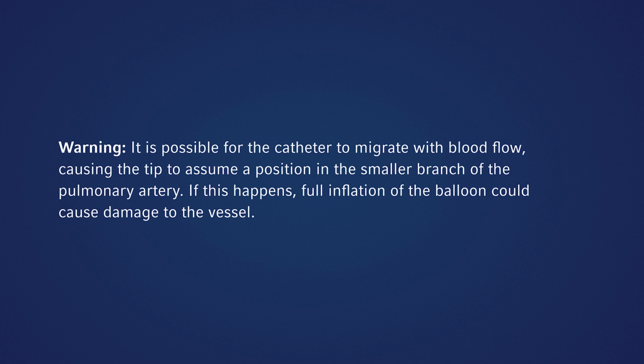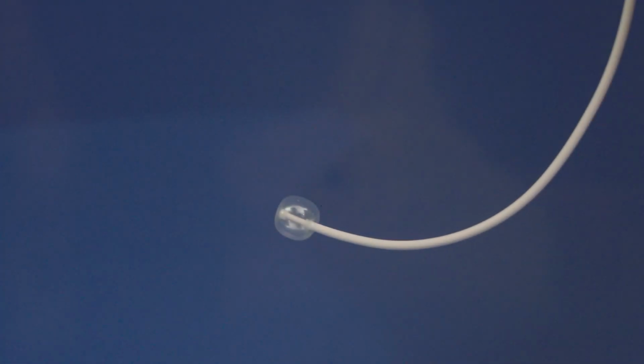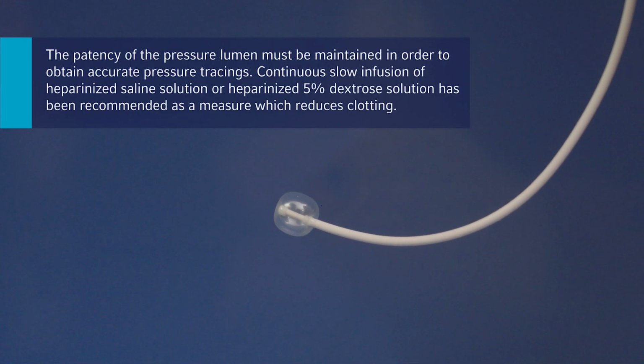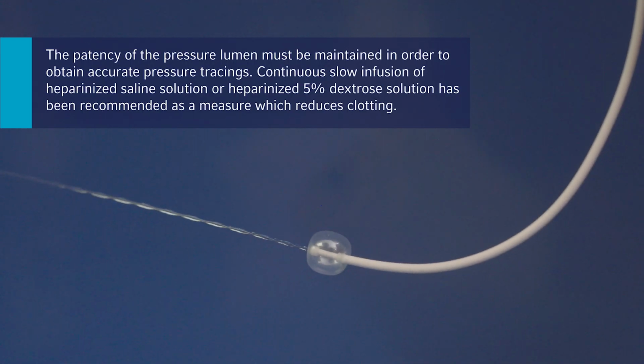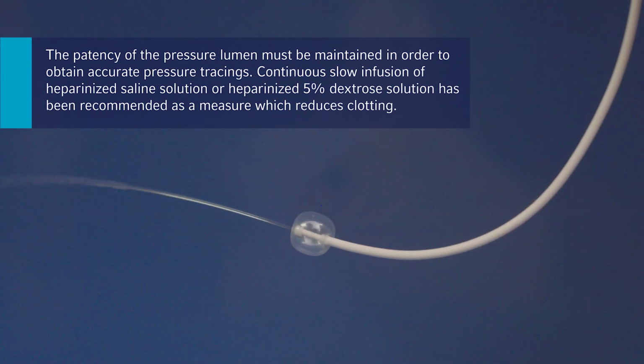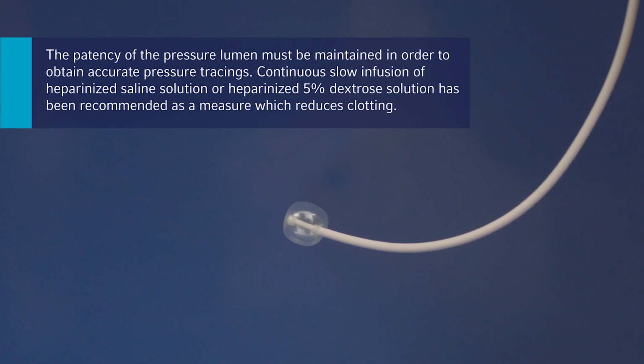Warning: it is possible for the catheter to migrate with blood flow, causing the tip to assume a position in the smaller branch of the pulmonary artery. If this happens, full inflation of the balloon could cause damage to the vessel. The patency of the pressure lumen must be maintained in order to obtain accurate pressure tracings. Continuous slow infusion of heparinized saline solution or heparinized 5% dextrose solution has been recommended as a measure which reduces clotting.